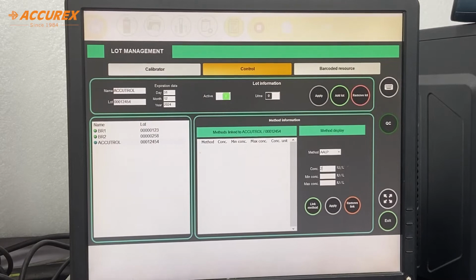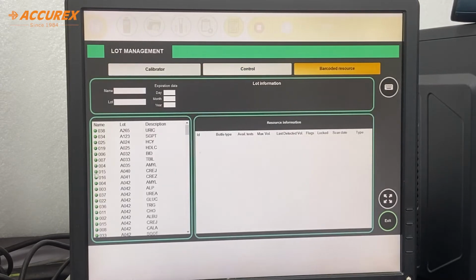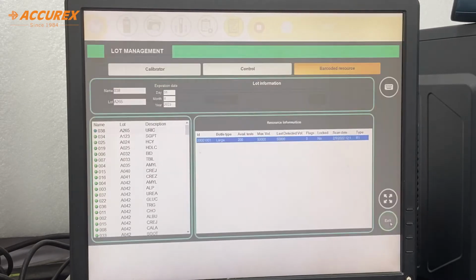Put the concentration, put the mean value, and link method. So once you click on the link method, it will get added over here. Okay. Then last is the barcode resource. Since it's a closed system, whichever barcode has been scanned for the reagent, you can see the date of calibration, the date of scanning when the bottle has been scanned, and the flagging and number of tests which will be performed on that. Okay, that's it.